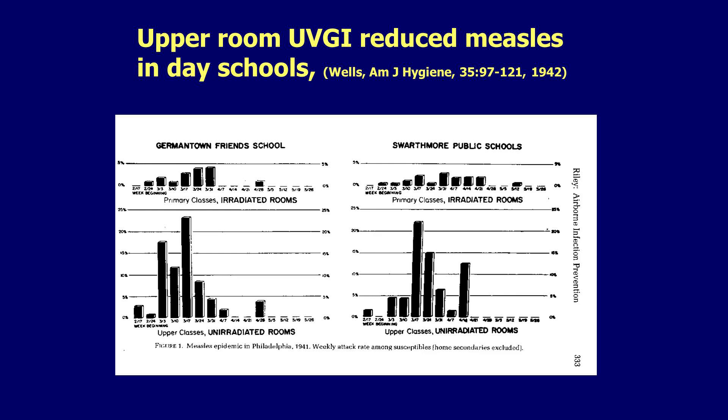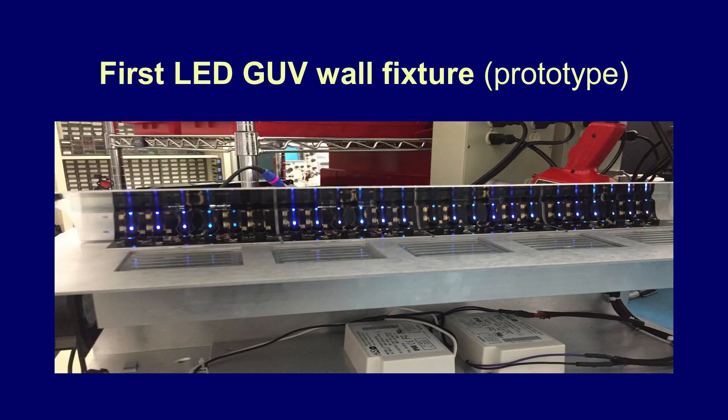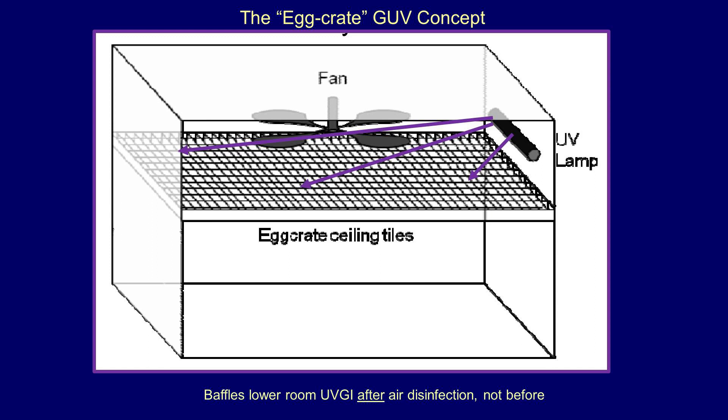You'll see the rate of measles per week. We have to be a little bit more careful with exposure of humans with 265 to 280 nm. This is a prototype UV fixture being tested in South Africa — now probably five or six years old. The pandemic has stimulated quite a bit of work on LEDs, but coming along it would look very different. Heat is a huge problem as well as power for LEDs at the moment. I was in the Moscow airport secondary terminal and noticed the egg crate ceiling and all the material above it, and wondered if we couldn't think about using more or less bare-bulb UV above an egg crate ceiling, blocking the UV from getting to the lower room with the egg crate, with the fan above or below. This has now been done commercially in custom installations.